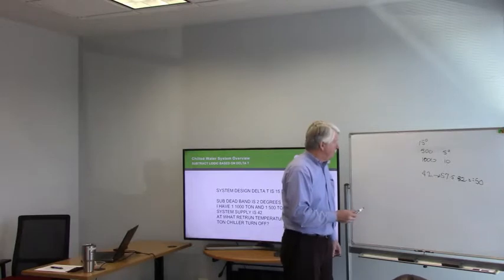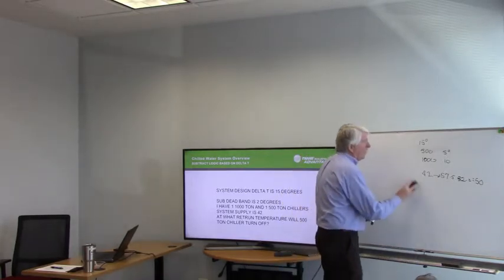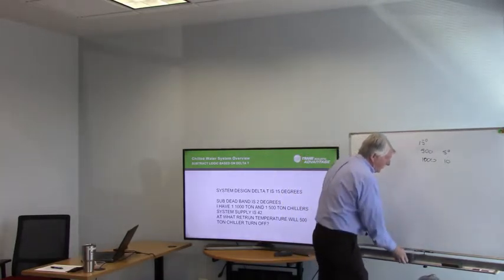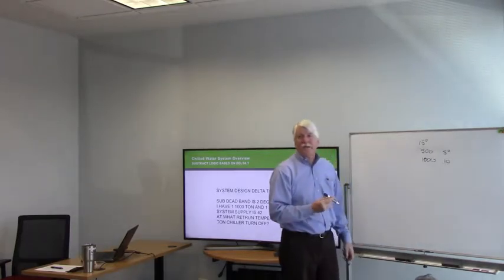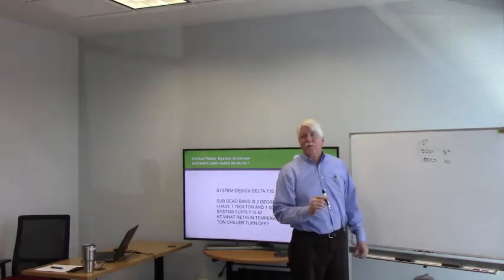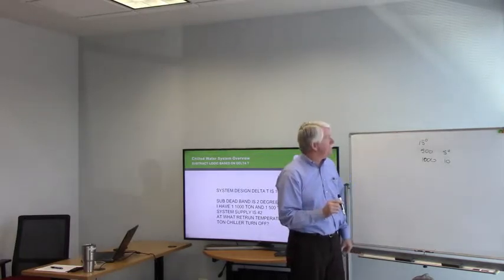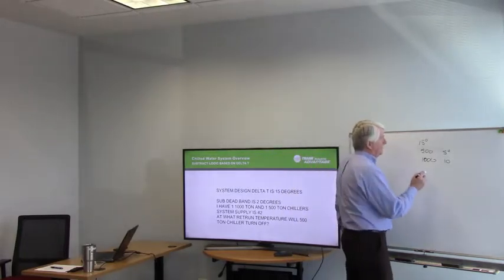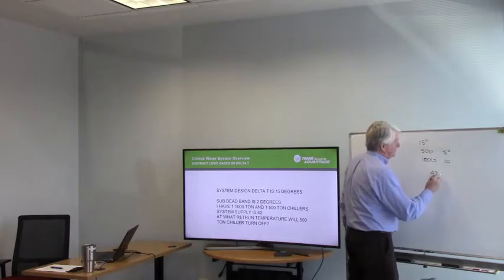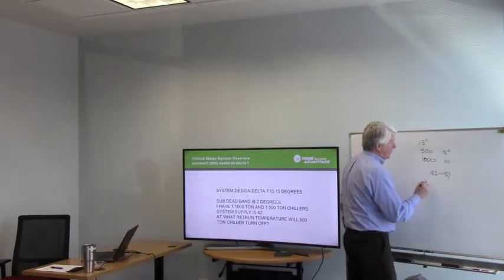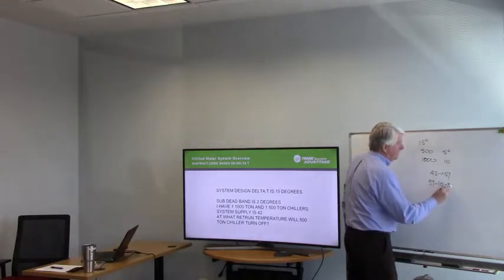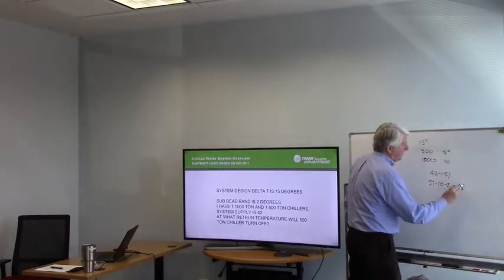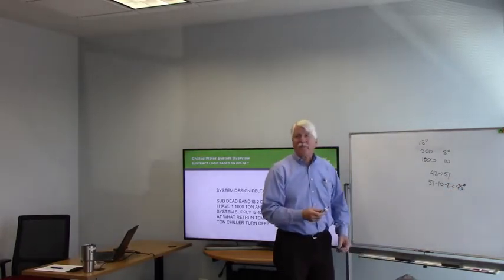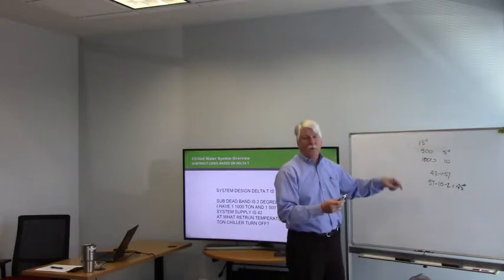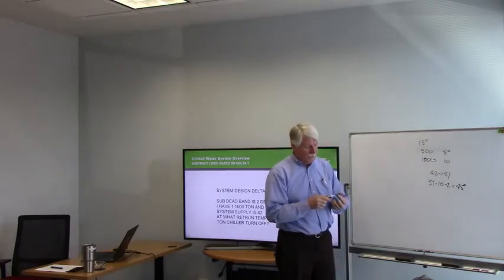All right. Now let's change the math. What happens if I decide I want to turn off the 1,000-ton chiller and I'm running 1,500? What does the return water have to be then? Okay. So we take 57 minus 10 minus 2, is 45 degrees. So if we want to turn off that 1,000-ton chiller, we've got to wait till that return water gets all the way down there. Okay?